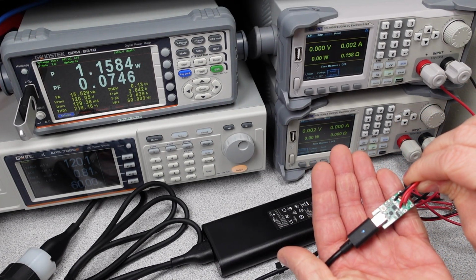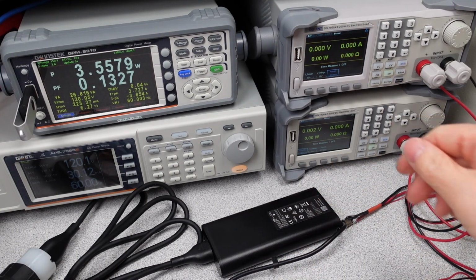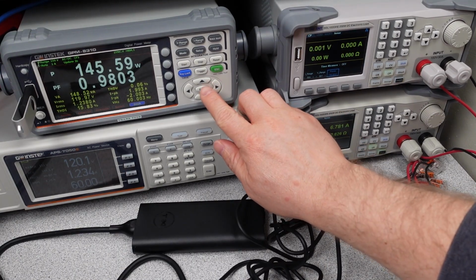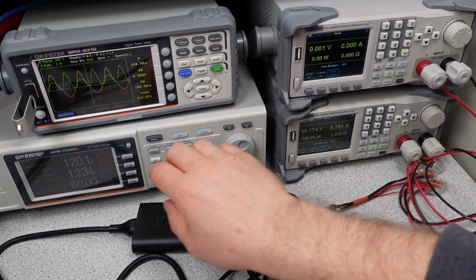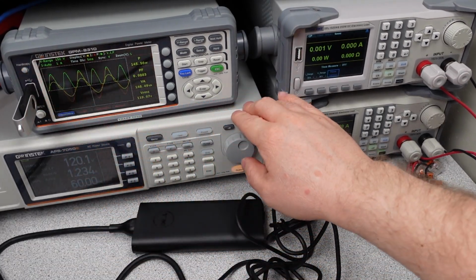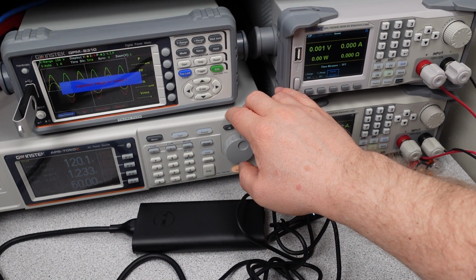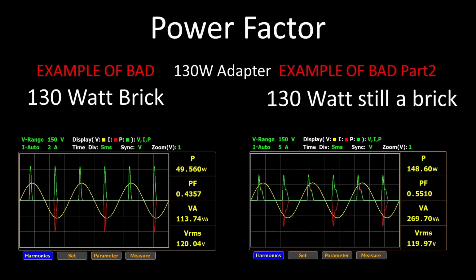The power factor correction is a technique to consume AC power as efficiently as possible. The higher the power factor, the lower the comparable current, and therefore the lower the loss in wires and transformers that supply your power. The goal is to have all the waves look like the same shape as the yellow line, a sine wave.